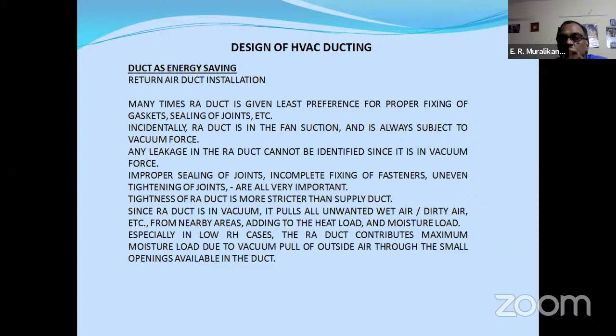How will you build positive pressure? You cannot do positive pressure. Or you have to separately put a blower during testing and commissioning, pressurize the duct and identify the leakage, which is very impractical. So here, I want to emphasize that any leakage cannot be identified since it's vacuum. Improper sealing of joints, incomplete fixing of fasteners, and uneven tightening of joints are all very important. Tightness of the return duct is more strict than the supply duct. The supply duct you can see the leakage, return duct you cannot see.